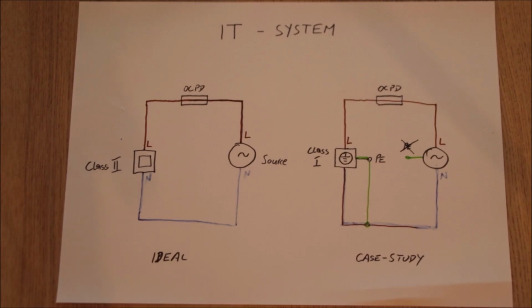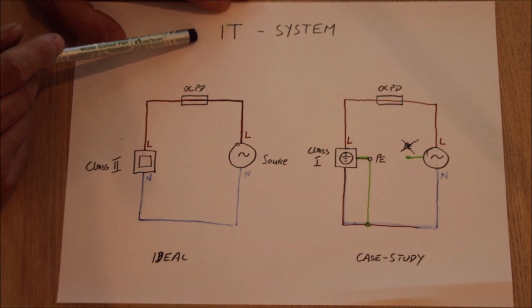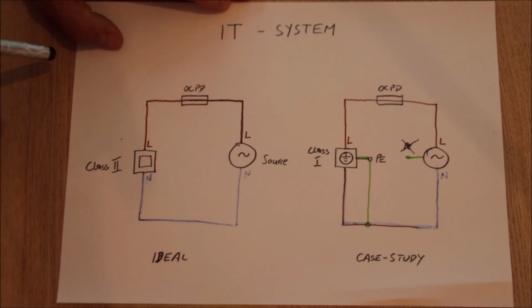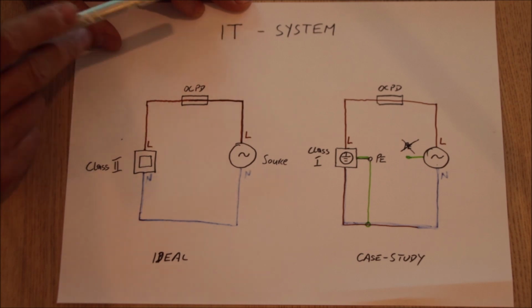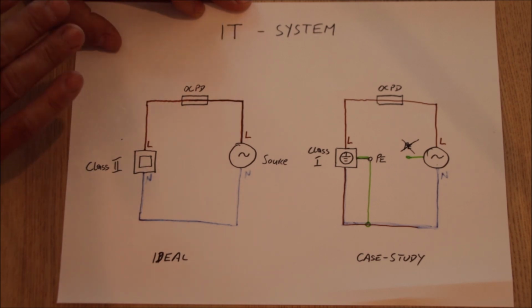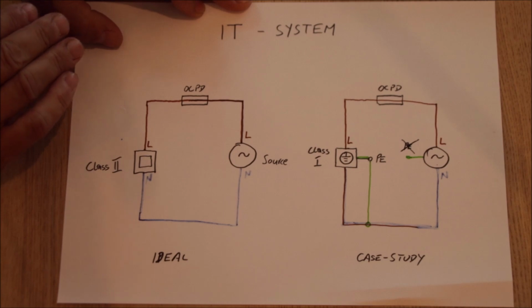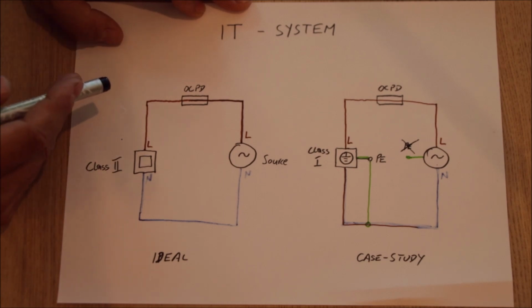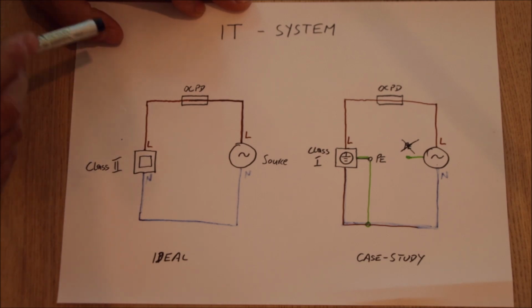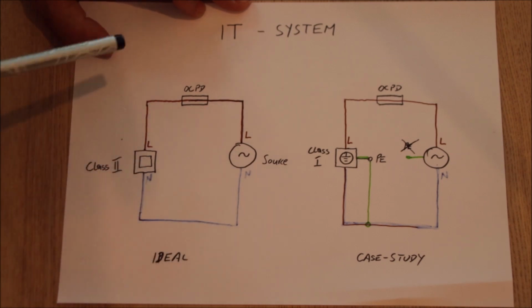I think this time we need to talk a little bit about the IT system. The IT system is counted as one of our earthing systems, but interestingly that system comes without earthing. So that's the speciality of this. IT, isolated terra, means the protection of this system is purely based on isolation and insulation. So how would the IT system in the ideal case look like? This here is the ideal case.